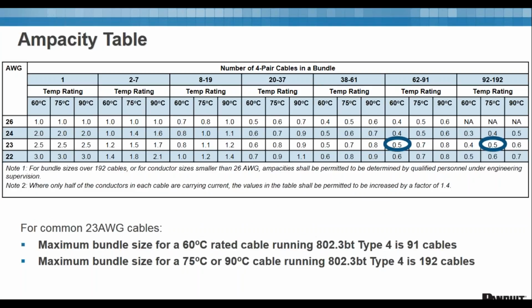Here's an example of the ampacity table. This is taken out of the code. What you can see here is that on the left, it says wire gauge: 26, 24, 23, 22. Then you have 1, 2 to 7, 8 to 19, 20 to 37, et cetera, up to 92 to 192. That refers to bundle size. Then under that, you see temperature rating, and then you have 60, 75, 90. That refers to your cable's operating temperature rating.